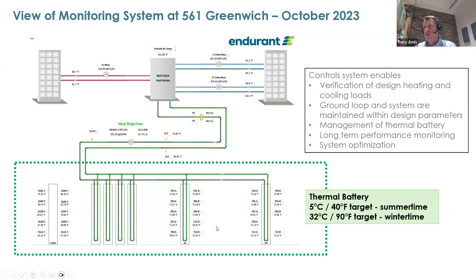So February 2024, what we are seeing is we're now delivering lots of heating to the building. And the idea through the winter is to use our thermal battery and drive the temperature down to about 40 degrees Fahrenheit in readiness for the summertime, so that we can then deliver really efficient cooling to the building. So we're treating the ground underneath this building, whilst the foundations are supporting the building, but it's also providing a significant chunk of the heating through the winter here.